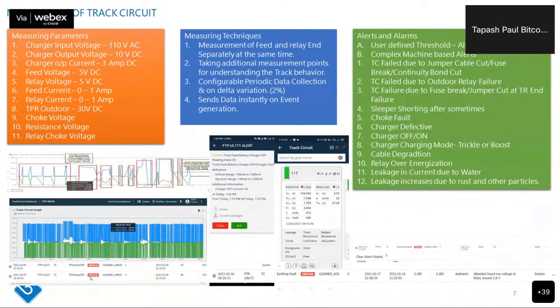Leakage increases. There are two types of leakage. One is whenever rain is coming, so leakage is increasing, and one is due to rust or other particles, where the real current is increasing and the leakage is increasing. So we distinguish between the two and give the alarms. Next.